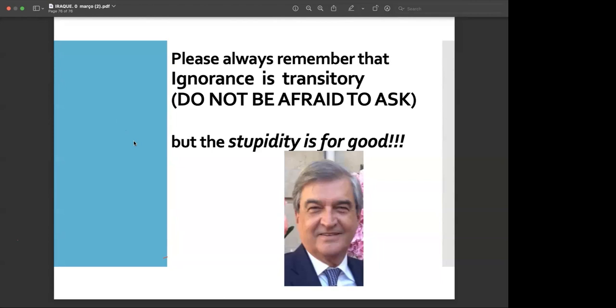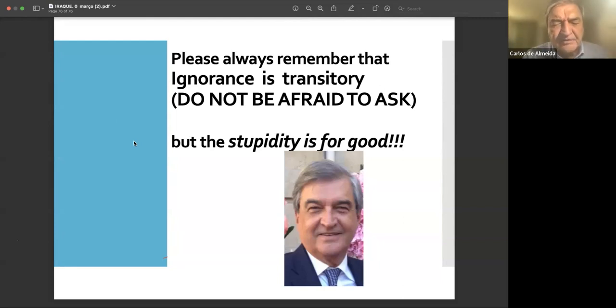My question is, what's the difference between absolute dosimetry and reference dosimetry? Okay, let's go back to one of the first slides. Absolute dosimetry is when you measure the quantities in the absolute way. You measure charge per unit of mass, for instance. Reference dosimetry is one where you have to use a calibration coefficient that was provided by a lab that has used an absolute way, like a calorimeter, ferrosulfate, or a free air chamber, to provide you with a calibration coefficient of your chamber, because you don't know the absolute volume of your chamber.